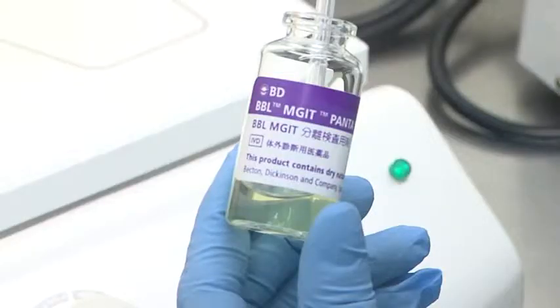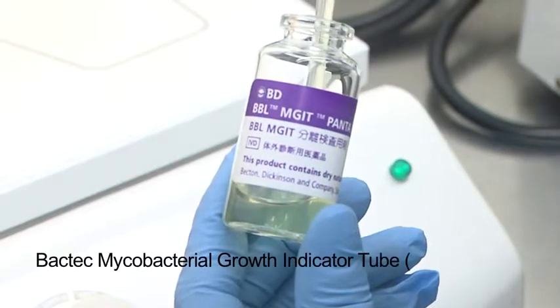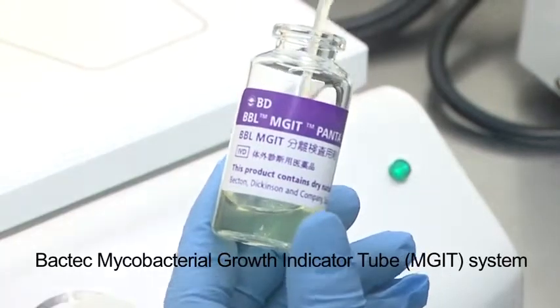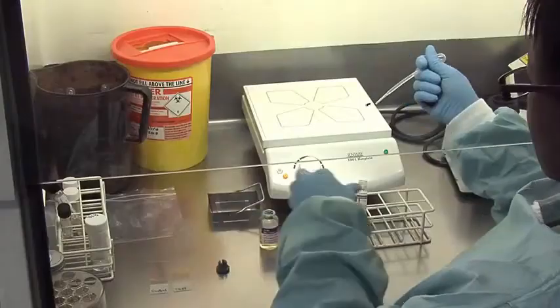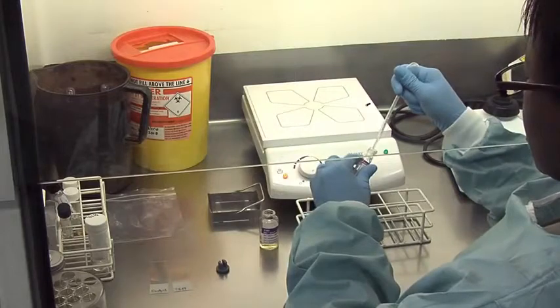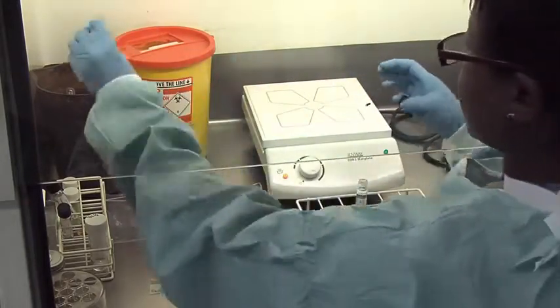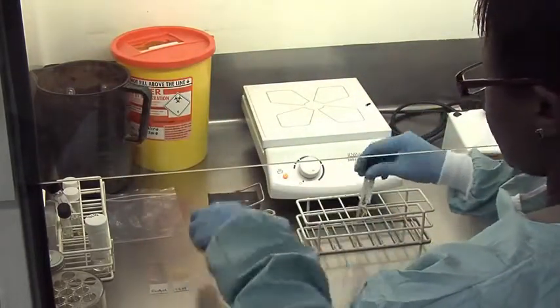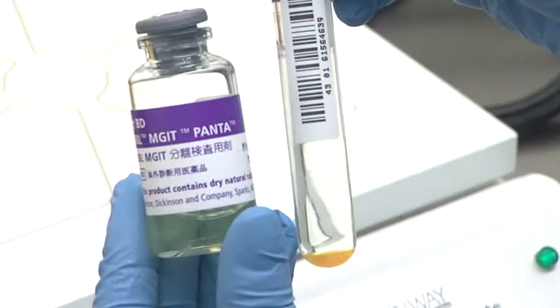The liquid culture media is a commercial-based system for mycobacterial culture. It is known as the BACTEC Mycobacterial Growth Indicator Tube System, with the acronym MGIT, or MIDGIT. The MIDGIT tube contains a modified Middlebrook culture broth and an antibiotic supplement. Growth of mycobacteria depletes the oxygen present in the medium. There is a layer containing a fluorophore at the bottom of each MIDGIT tube, and reduction in oxygen level activates this.